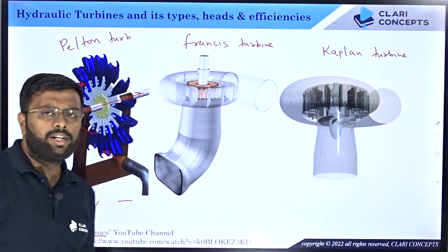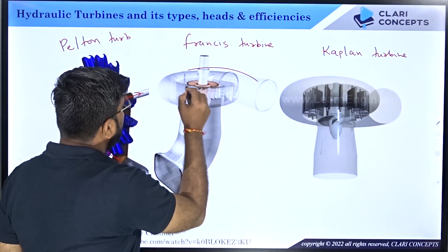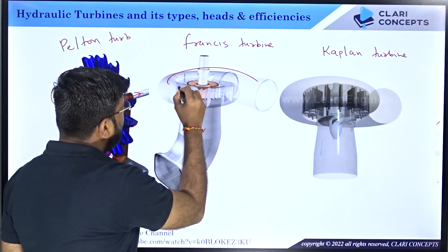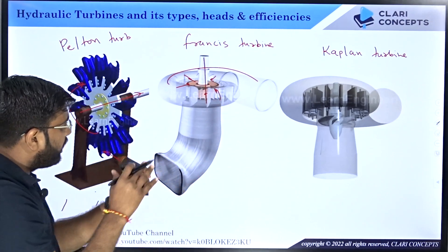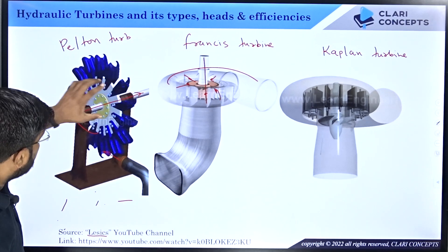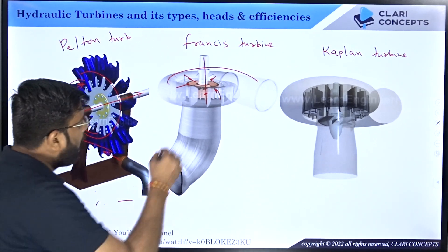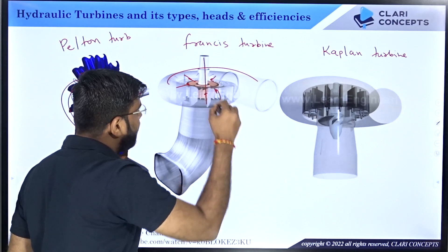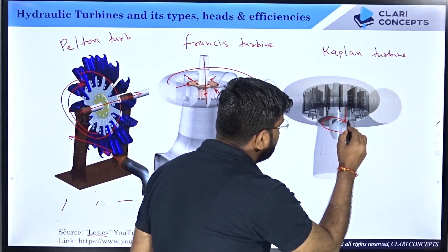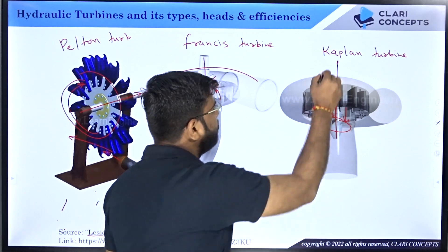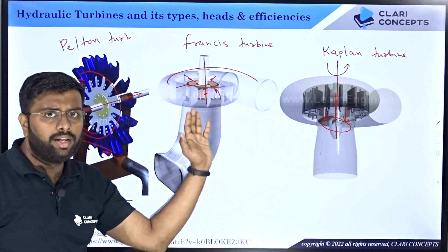This is the shaft which transfers your mechanical energy to the generator. This is the whole mechanism — this is called the Pelton turbine. For Francis turbine, water enters here, and the runner is arranged differently — the shaft is like this and water flows radially. In Pelton, the bucket arrangement and water jet are tangential to the runner circle — this is tangential flow. The runner in Francis has radial flow. The third type is the Kaplan turbine, where the shaft is vertical and water flows axially along the axis.